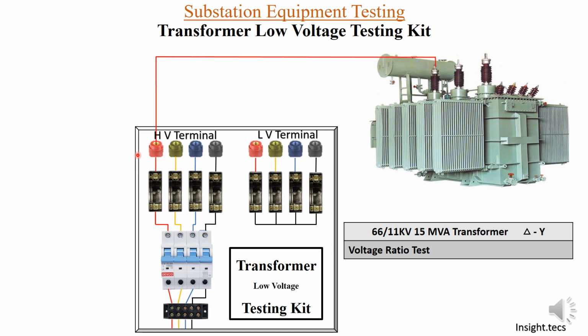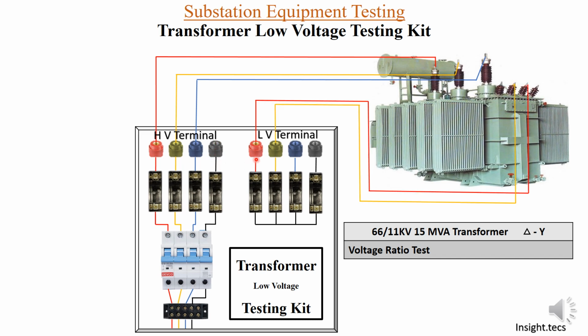Now let us connect all the HV terminals on the HV side of the transformer. So R phase, Y phase, B phase connections are provided. Next you have to see that the HV side of the transformer is delta connected, so there will not be a neutral connection. Next we will move towards the LV terminals and provide R, Y and B connections over here, and the neutral connection.